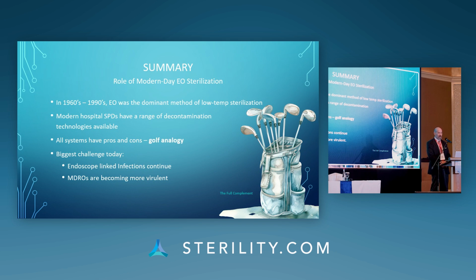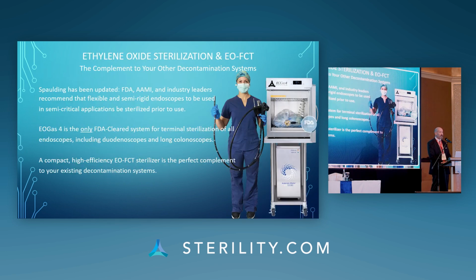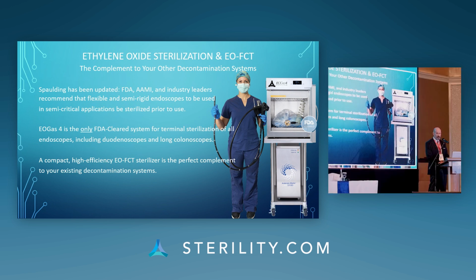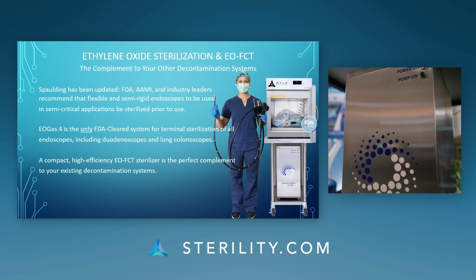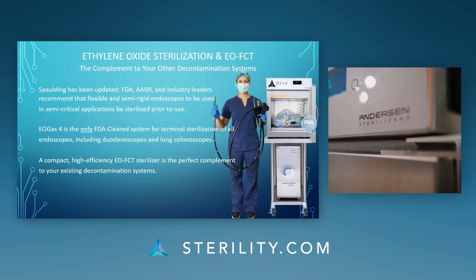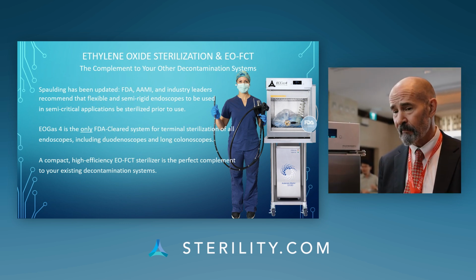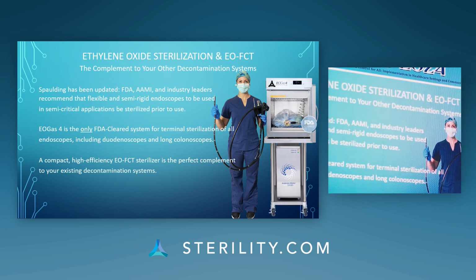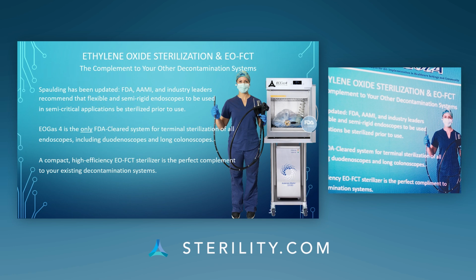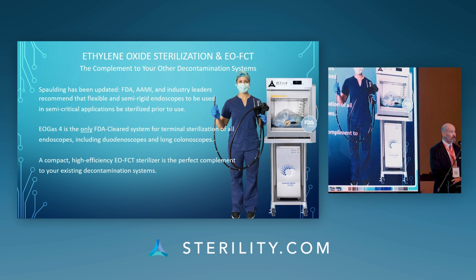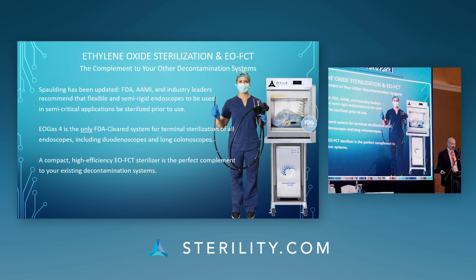And I'll come back to the challenges that we were talking about earlier in this presentation, specifically the growing threat of endoscope infections and the growing threat of multi-drug resistant organisms. These are two problems that are not going away. Spaulding has been updated. FDA, AAMI, and industry leaders are now all calling for the sterilization of flexible and semi-rigid endoscopes used in semi-critical applications. Again, this is a major change. It hasn't happened across the United States, but this is the direction that the industry is moving. And flexible chamber ethylene oxide systems and the Andersen EO-Gas 4 are the only systems that have been cleared by FDA for the terminal sterilization of longer endoscopes: duodenoscopes, gastroscopes, colonoscopes.